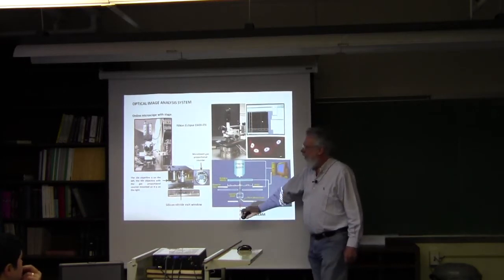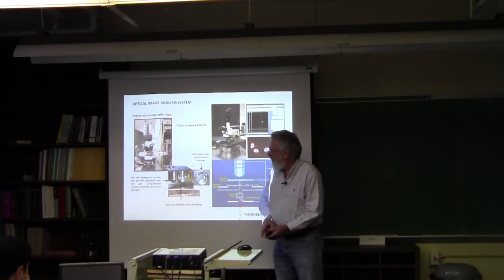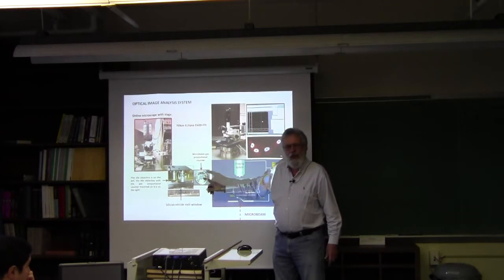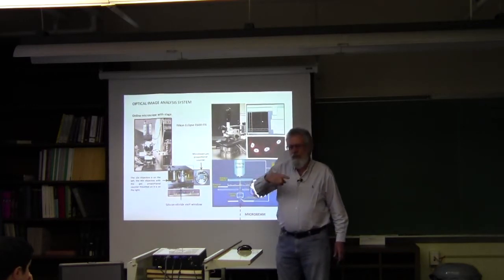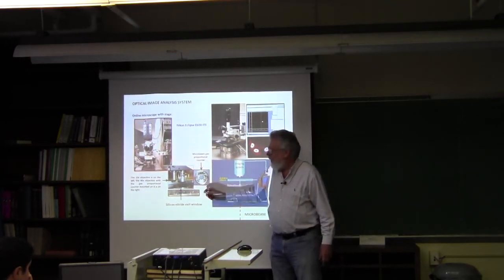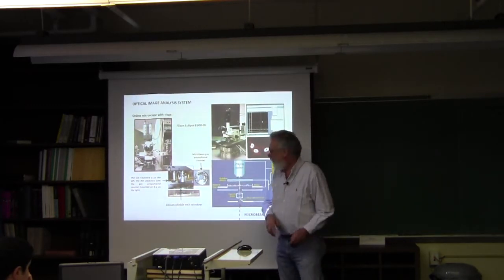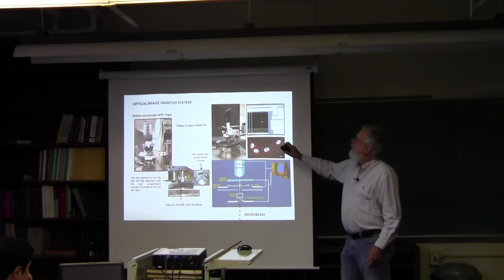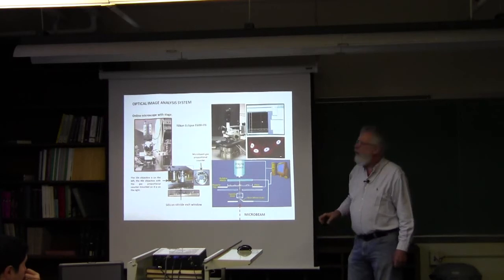This is the blown-up picture of the counter. We have a smallish aperture, an eighth of an inch hole coming in the middle, so the ions are produced in the gas here as the particles come out. Off to the side there's a metal wire helix to produce the outside surface of a proportional counter. There's a very fine wire down the middle where the ions are collected. That gives a pulse every time a particle comes through the middle. We'll do some practicing with this tomorrow.